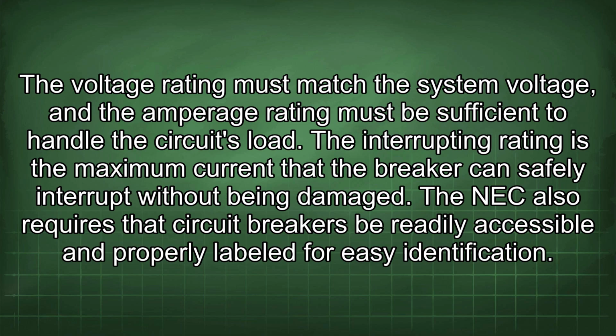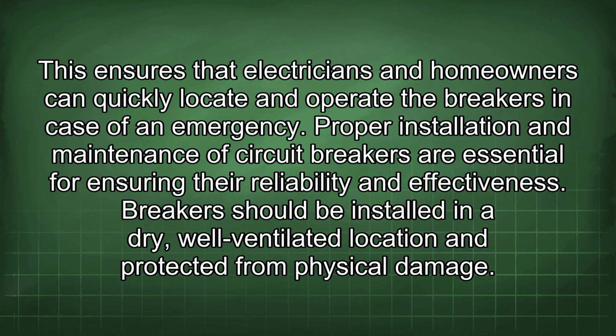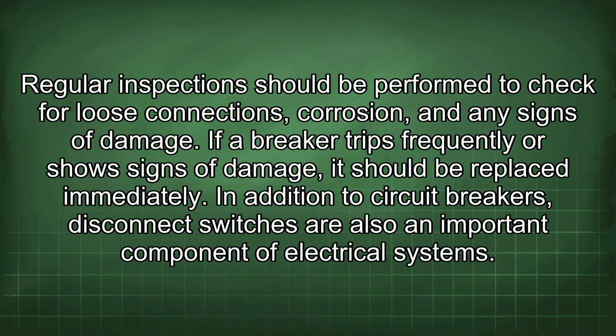The NEC also requires that circuit breakers be readily accessible and properly labeled for easy identification. This ensures that electricians and homeowners can quickly locate and operate the breakers in case of an emergency. Proper installation and maintenance of circuit breakers are essential for ensuring their reliability and effectiveness. Breakers should be installed in a dry, well-ventilated location and protected from physical damage. Regular inspection should be performed to check for loose connections, corrosion, and any signs of damage. If a breaker trips frequently or shows signs of damage, it should be replaced immediately.